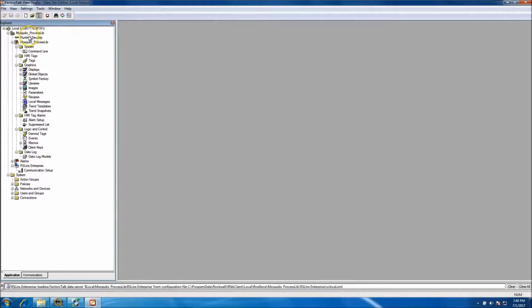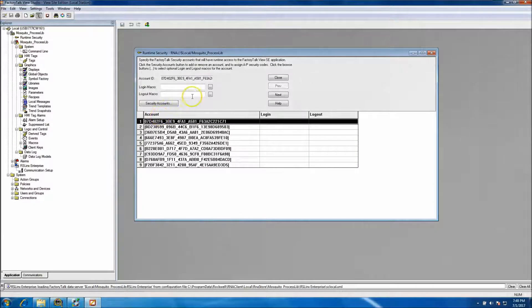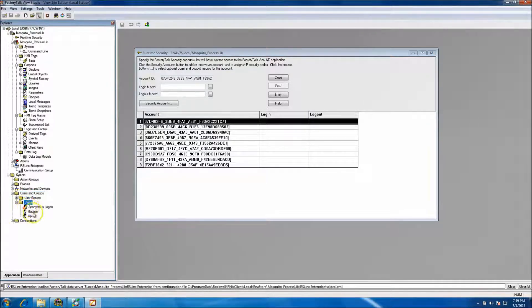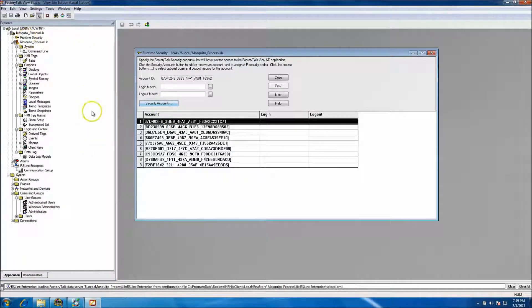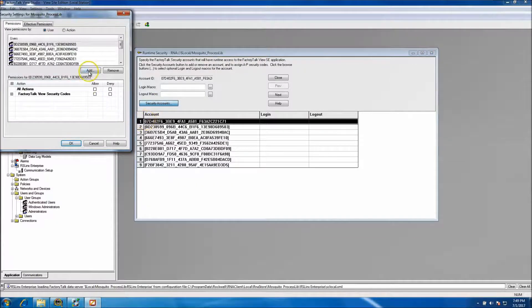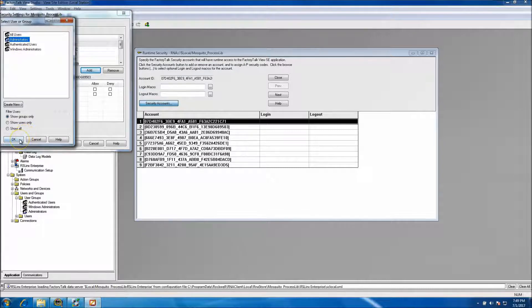The next thing you need to do so that you have access to run the client is go to Runtime Security. The runtime security will come up with a bunch of predefined stuff - you need to verify that you have a user in your system. If not, make a user, make a user group, and add it in. I'm an administrator so I'll use that. Open Runtime Security, go to Security Accounts, and add Administrators.